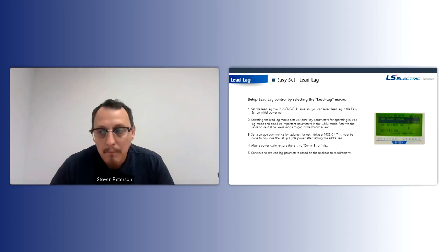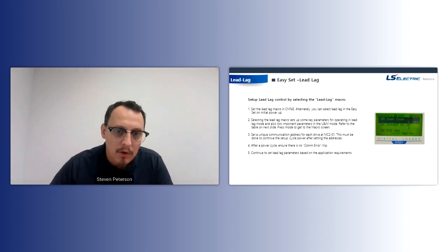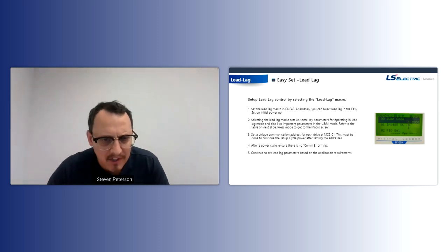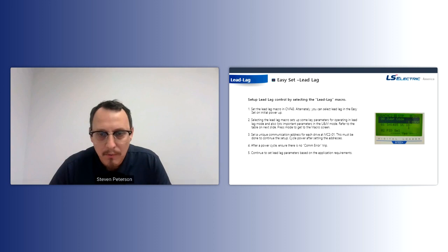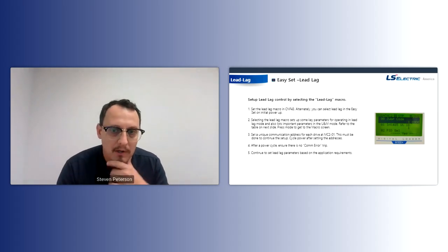We also recommend checking that you enabled your termination resistor on the last drive on the network. The line resistor is what that is. That's built into the drive. You just have to flip the switch. Anytime I mess with communications, I like to cycle power. After you cycle power, there should be no communication errors anymore, because when you first program this, you'll get a COM error until you set up your address appropriately.